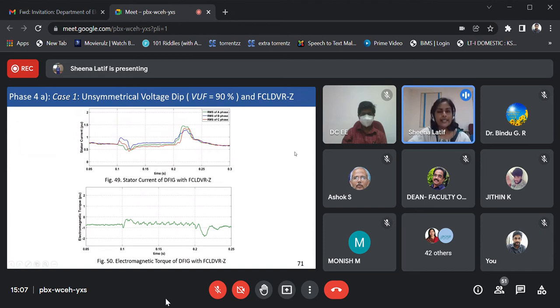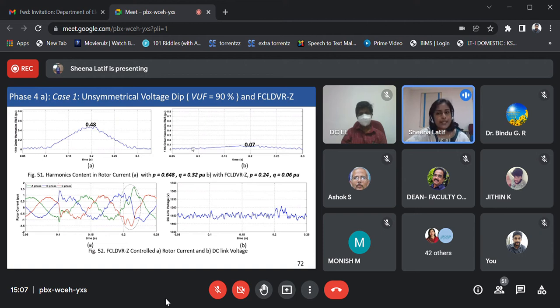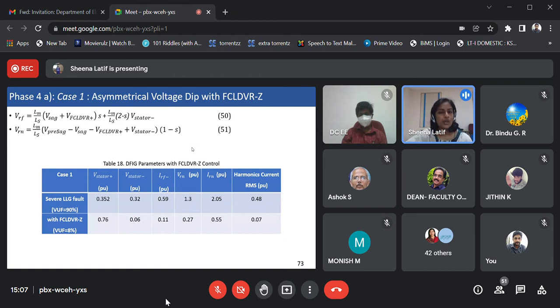We can see there is a slight rise in the stator current during the transient, during the fault clearance period. This is because the inductor current is still flowing through the SCR, the pulses take time for switching off, and the inductor currents are still discharging. The harmonics component is reduced from 0.48 to 0.07 for VUF equal to 90%, and the rotor current is regulated in steady state to 1 per unit value, but in the fault clearance period, similar to the stator current, there is a slight rise in the rotor current. So as VUF equal to 90% is considered for the FCL DVR impedance control method, the harmonics component is reduced from 0.48 to 0.07. The rotor natural current is reduced to 0.55, and the negative sequence rotor forced current is reduced to 0.11.